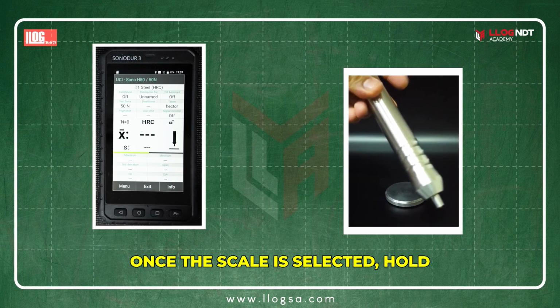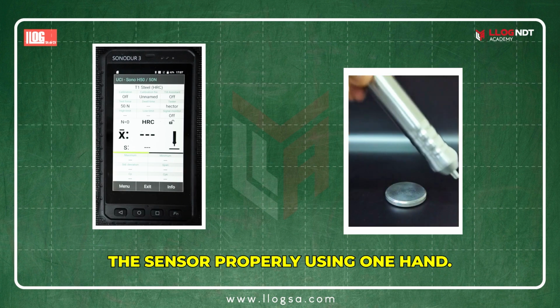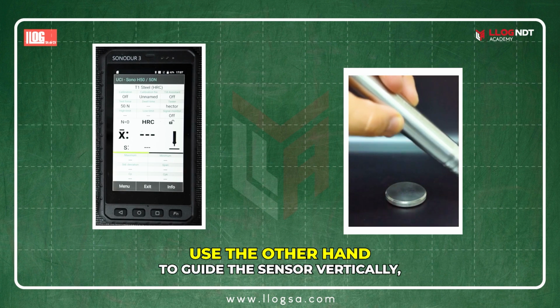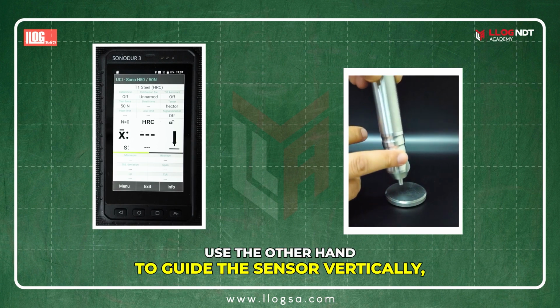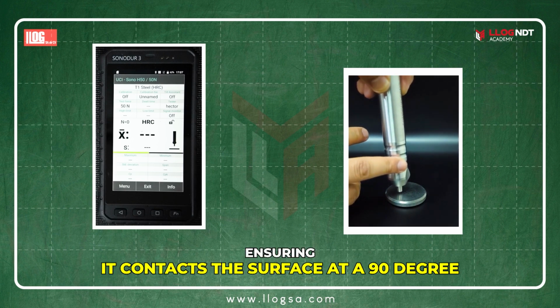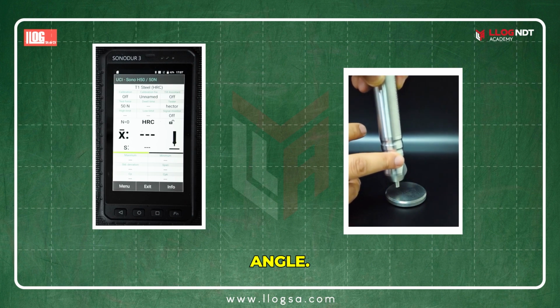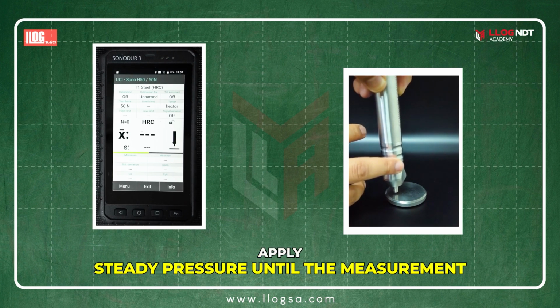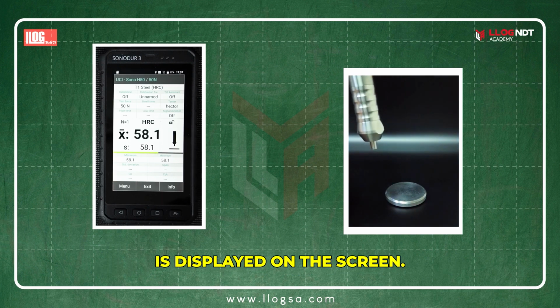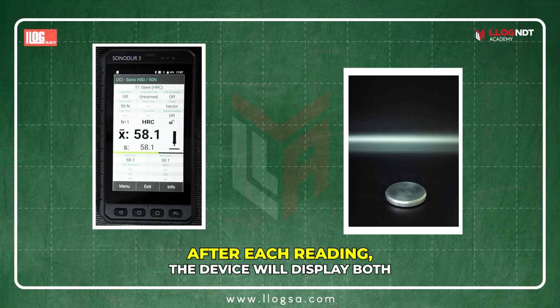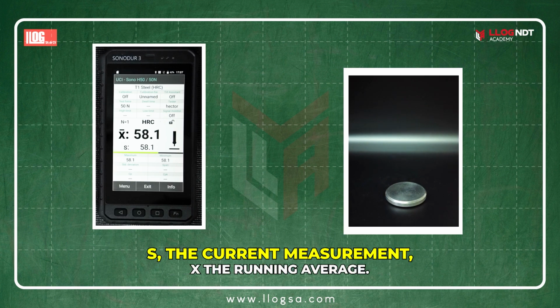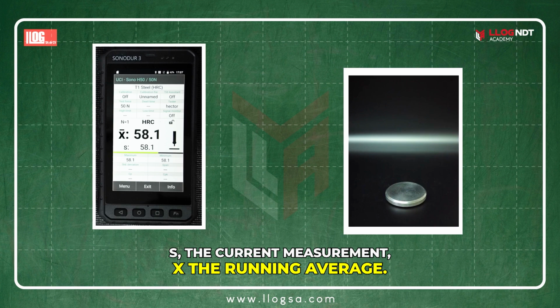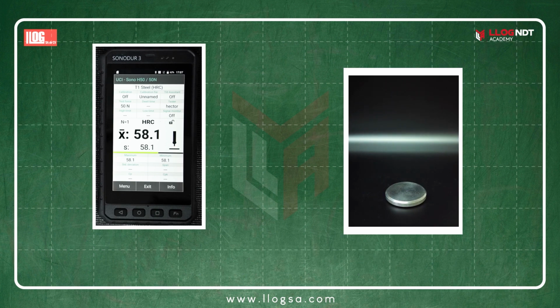Once the scale is selected, hold the sensor properly using one hand. Use the other hand to guide the sensor vertically, ensuring it contacts the surface at a 90-degree angle. Apply steady pressure until the measurement is displayed on the screen. After each reading, the device will display both S, the current measurement, and X, the running average.